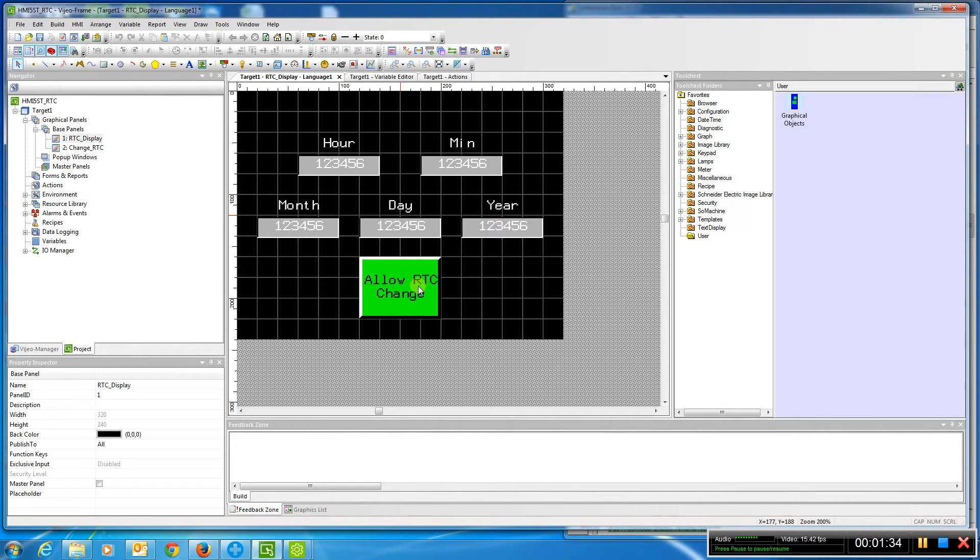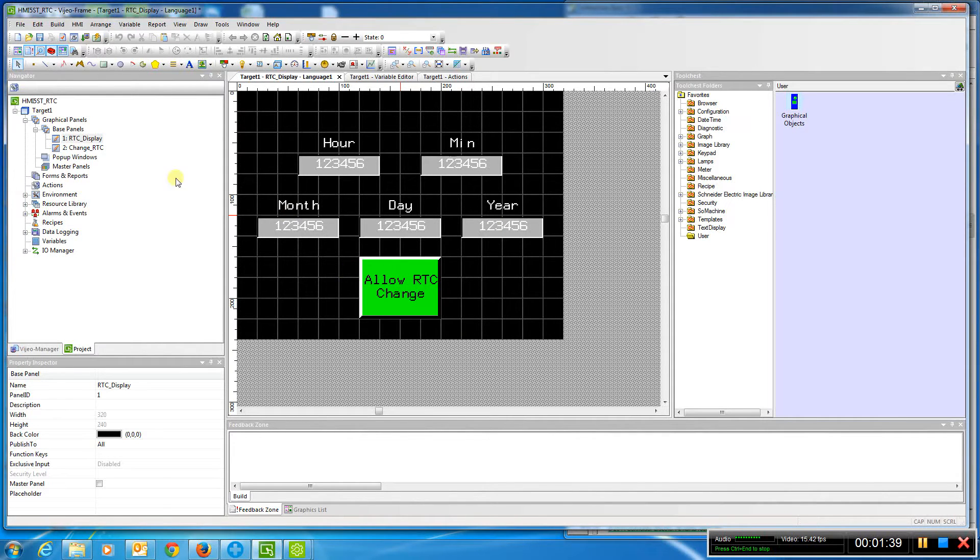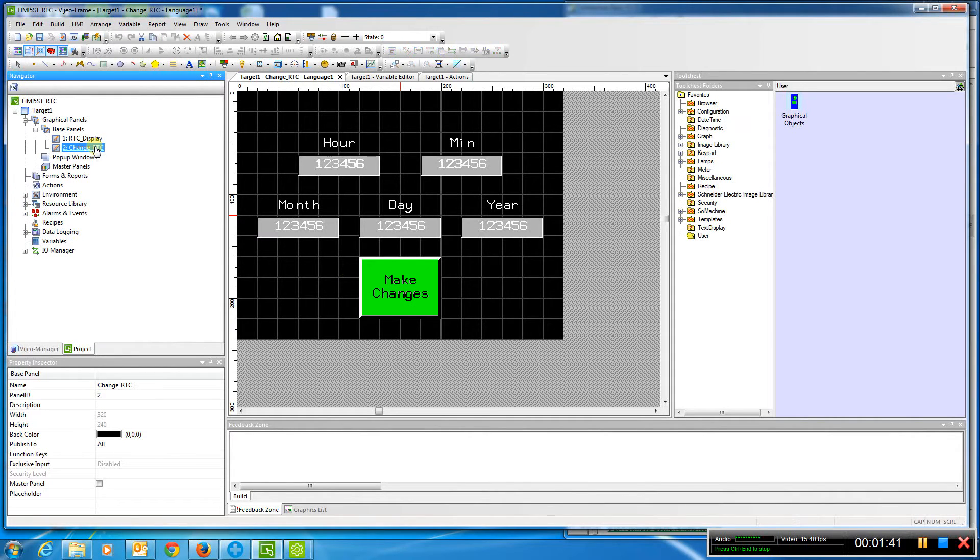If we want to change it, specifically in the M.221, we have to set system bit 50. So what I did is I created a separate page which is pretty identical, just a little button change here.